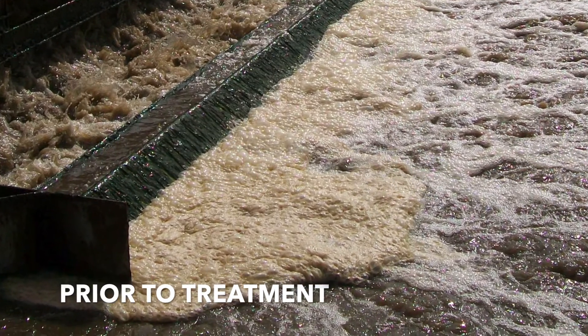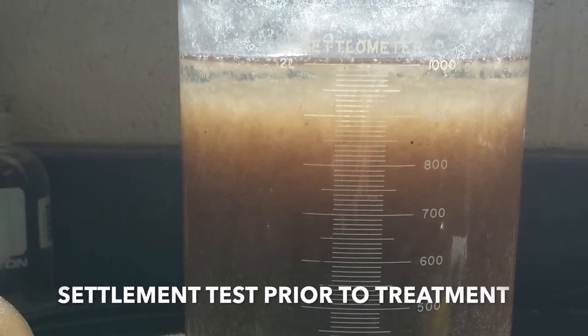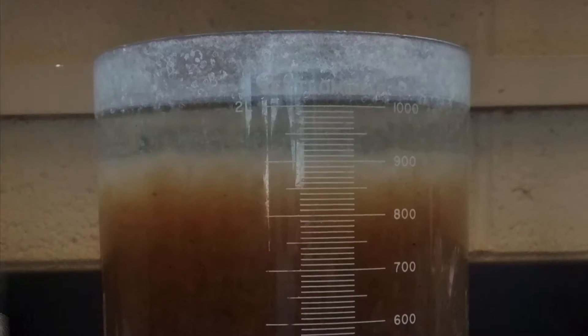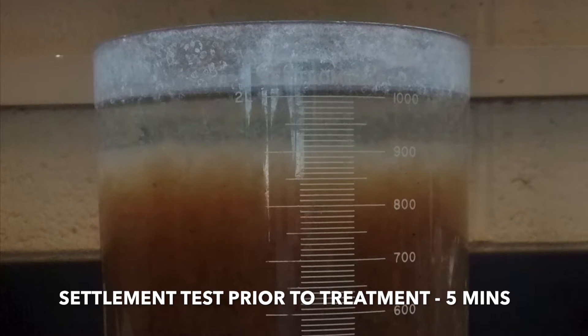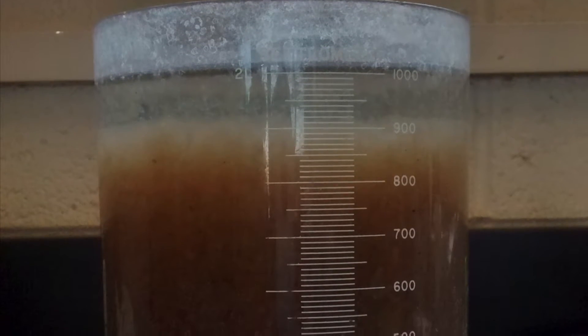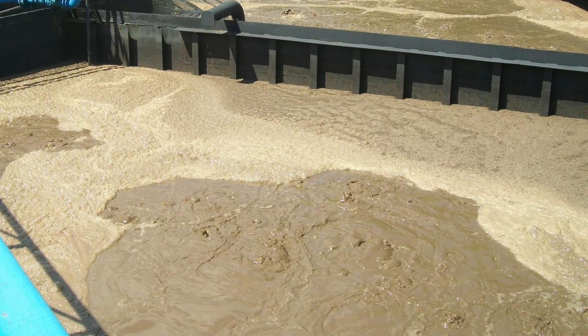A local facility began to experience trouble with settling and turbidity. The SVI was climbing from a typical range of 170 up to 400 and above. Regardless of what was done with wasting, aeration, or recirculation modifications, the SVI would not return to their normal range. Along with SVI problems, foam began to form in the oxidation ditches and also in the RAS channel.